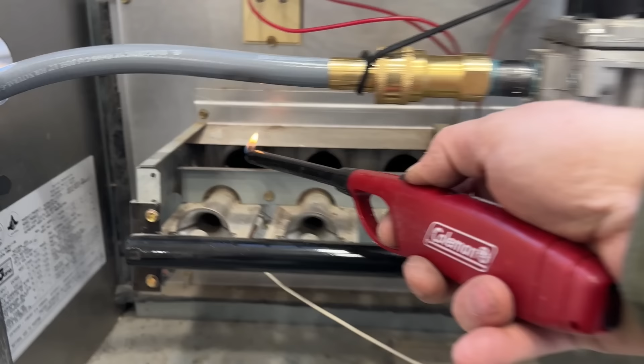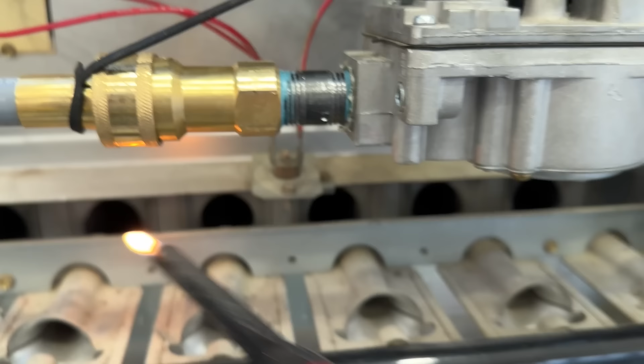I just wanted to show you this with a controlled flame. It has a set amount of gas coming out, and as you can see, that is extremely steady. If we go all the way over to the right side where we have this hole, you can see that flame is moving left and right. It's getting a steady supply of gas, so it's not putting it out because it's not that bad, but it's absolutely dancing - and that's what we're looking for.